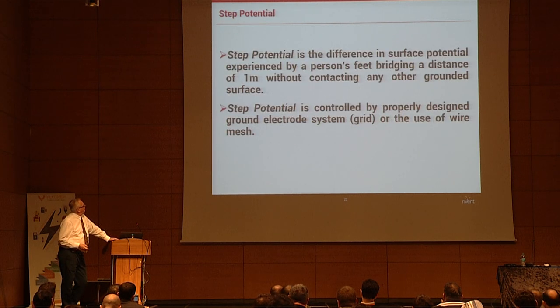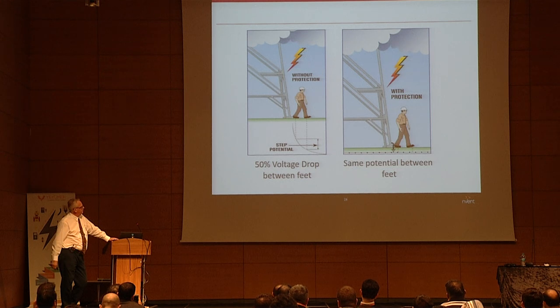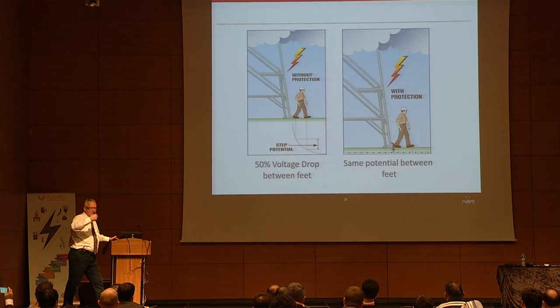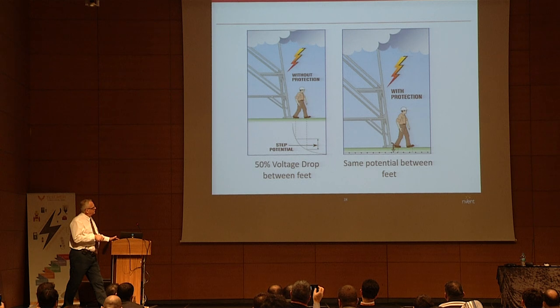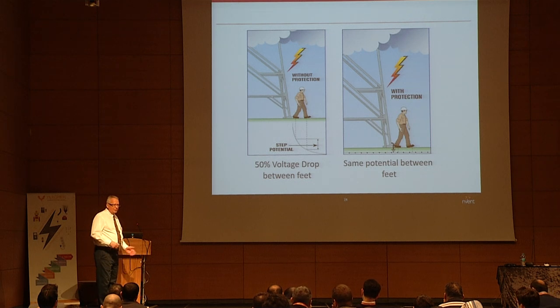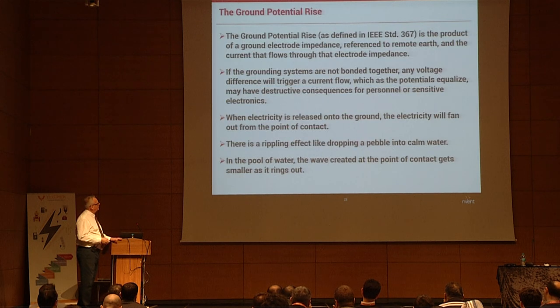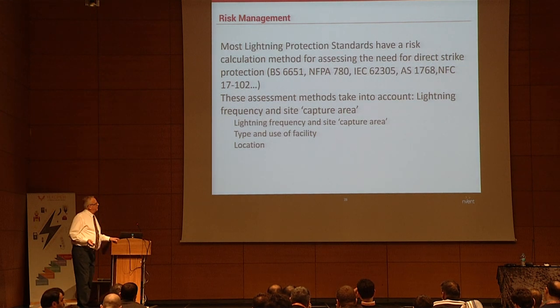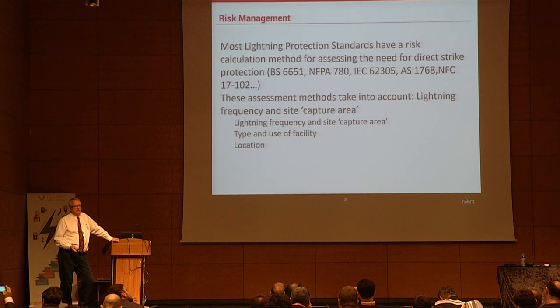Step potential: the same principle applies in a substation — with a meter between my feet I can get electrocuted by current passing through my body on native soil. With some type of mesh I am protected, or I would have to take very small steps to minimize the step voltage.